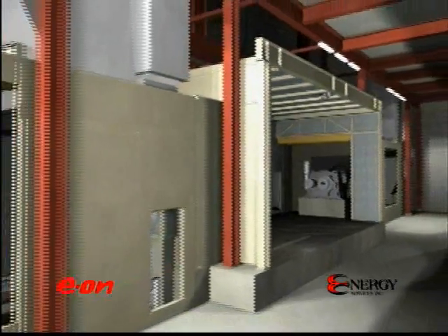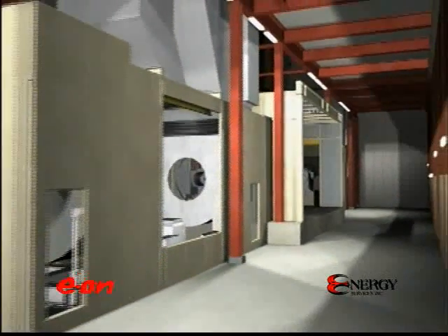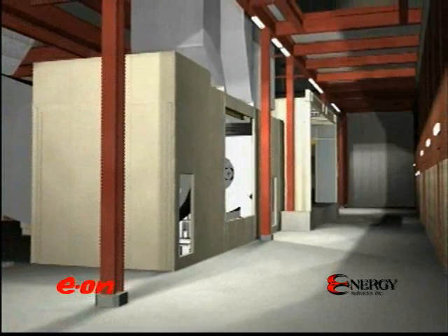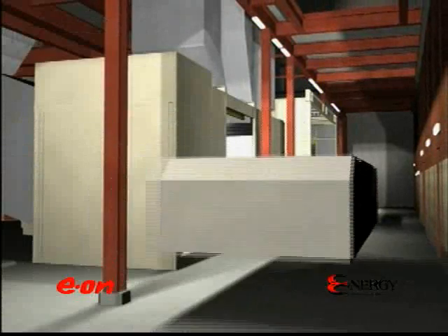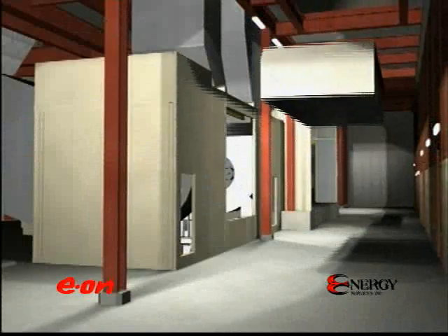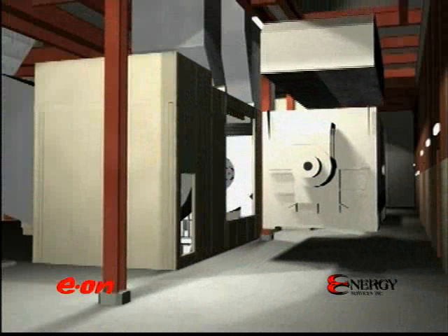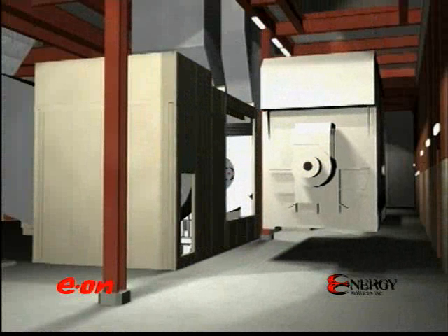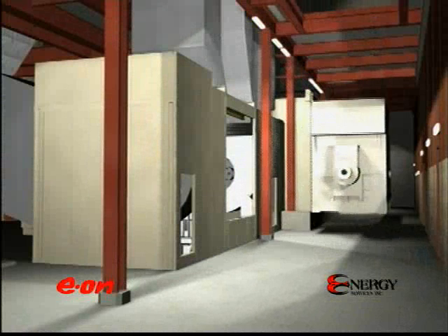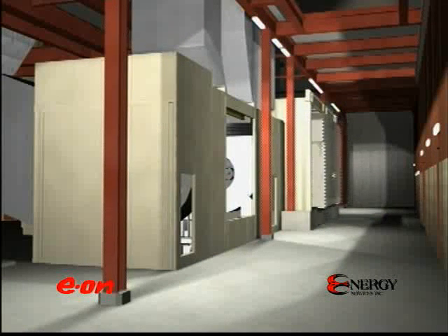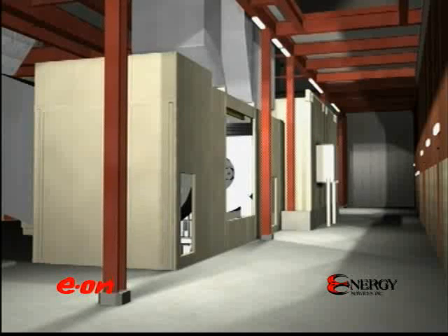The generator, with its cooler attached, was too tall to enter the building, so the cooler was removed, brought in, and raised using the existing bridge crane through the existing access opening in the first floor above. The generator was brought in, and the cooler reassembled to it. The complete generator and cooler assembly was then moved into the generator enclosure. The line side and neutral cubicles were installed, and then the framing and wall panels of the generator removal wall were assembled, completing the generator enclosure.